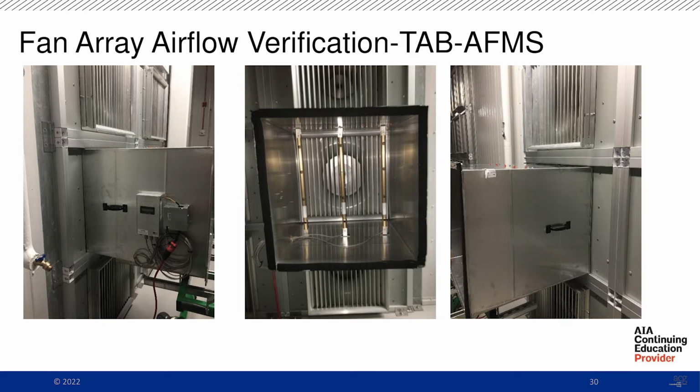As you see here, it sits right on the fan. It's a 27 by 27. It's a rectangle here, and like I said, I think this is without the extension sleeve on it. We only used the extension sleeve when we needed. We were verifying it with our traverse. We also did traverses without it on, and I believe later in the project we just ended up getting rid of the extension sleeve because our traverses were always true.